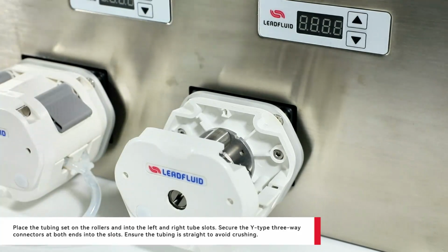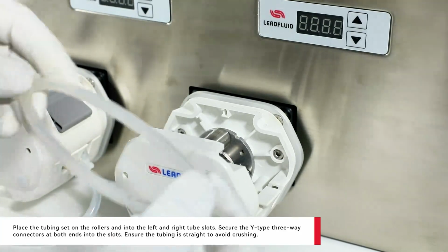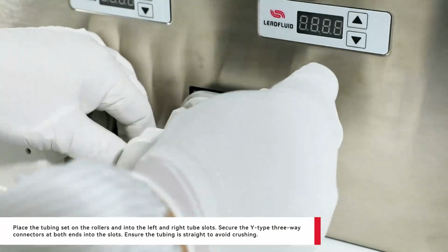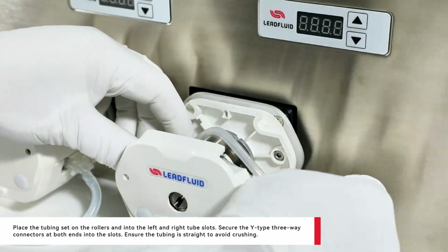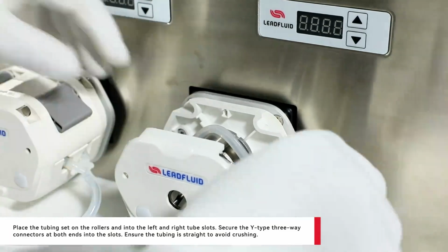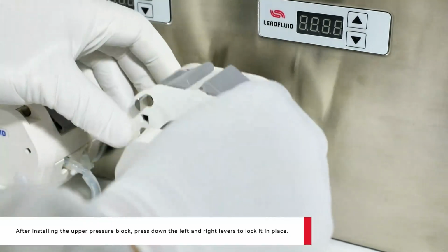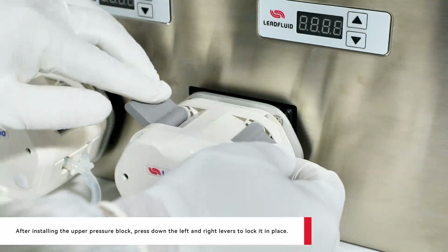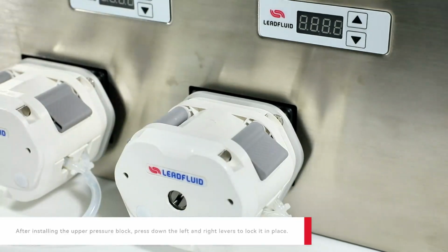Place the tubing set on the rollers and into the left and right tube slots. Secure the Y-type 3-way connectors at both ends into the slots. Ensure the tubing is straight to avoid crushing. After installing the upper pressure block, press down the left and right levers to lock it in place.